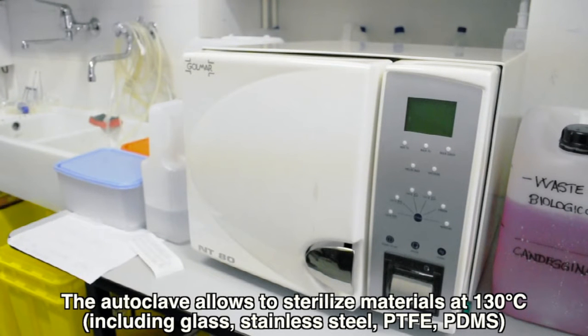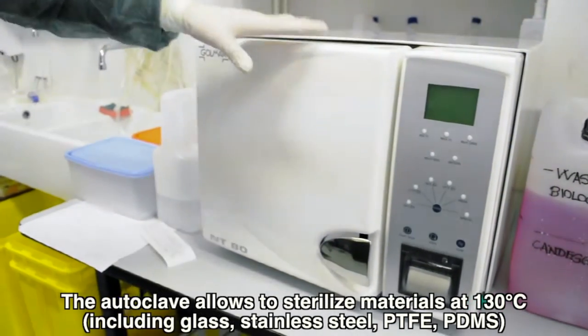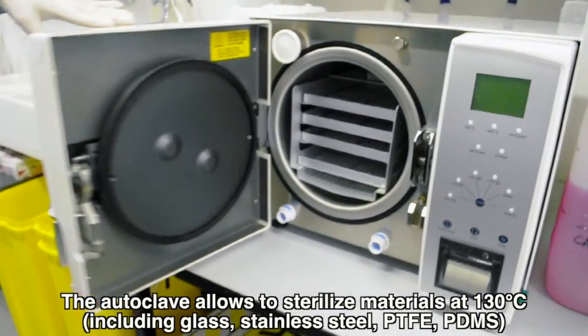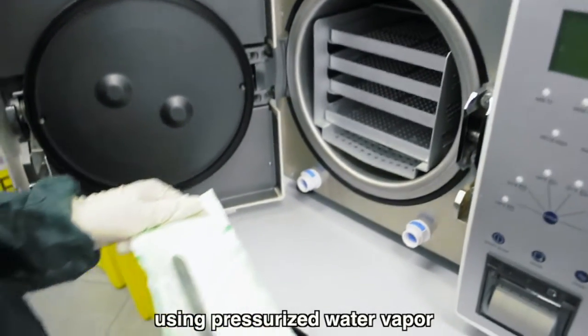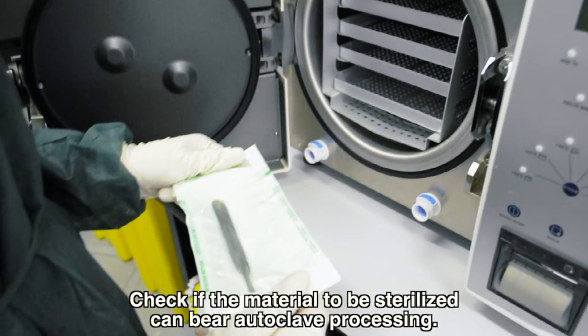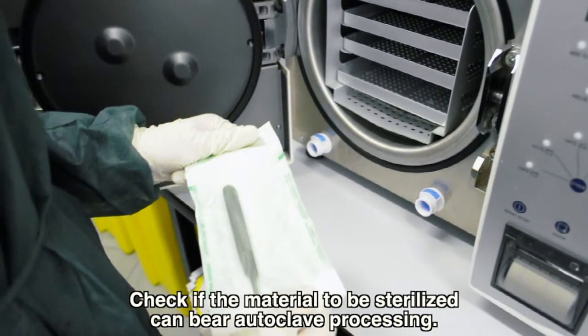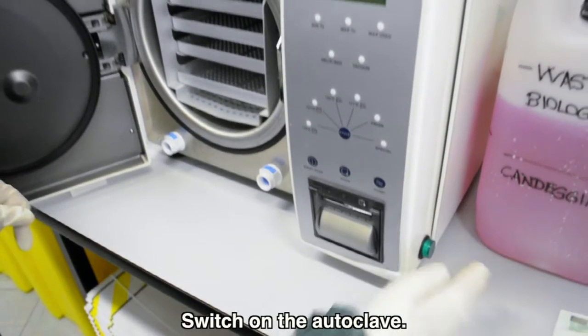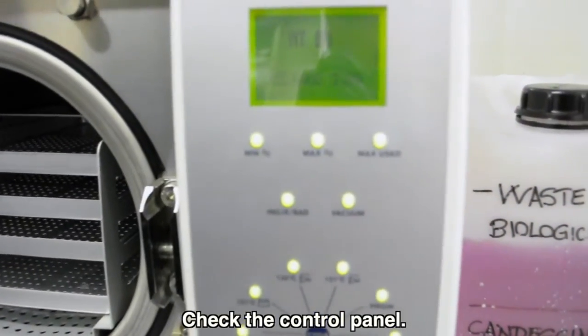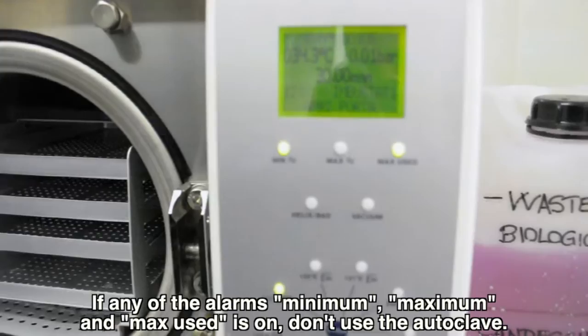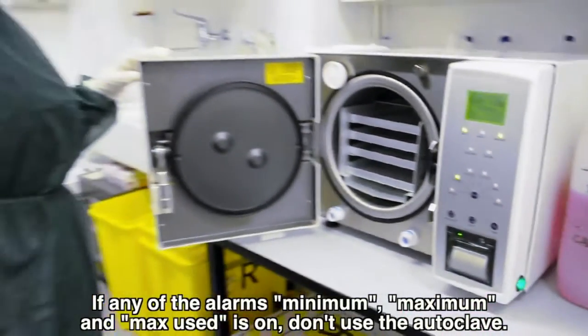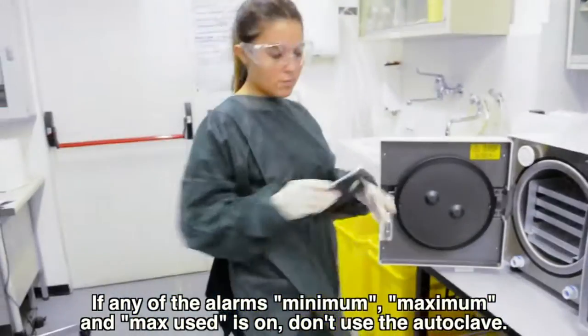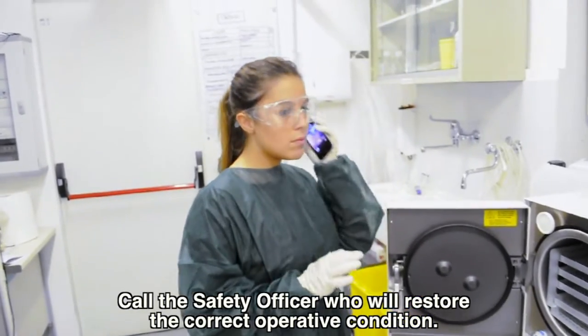The autoclave allows to sterilize materials at 130 degrees, including glass, stainless steel, PTFE, PDMS, using pressurized water vapor. Check if the material to be sterilized can bear autoclave processing. Switch on the autoclave. Check the control panel. If any of the alarms minimum, maximum, and max used is on, don't use the autoclave. Call the safety officer who will restore the correct operative condition.